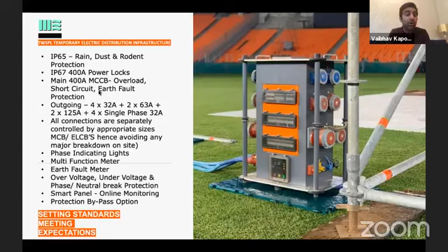Once we have done that, on the show day, we switch off all the safeties. That means I switch off my ELCB, I switch off my over or under voltage, because I know that the genset has been running for a fair period of time. So I switch off the safety only for those short timings, maybe for 3 or 4 hours.